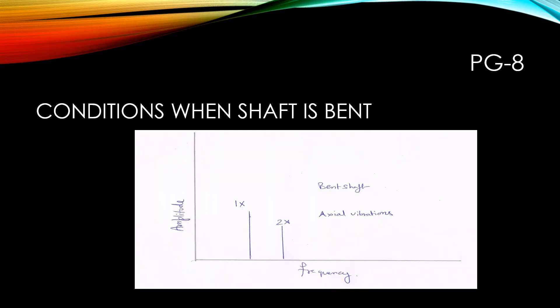Now the case where there is a bent in the shaft. When the shaft bent is encountered, the vibration in the radial as well as in the axial direction will be high. The axial vibration may be higher than the radial vibrations. The spectrum analysis will normally have 1x and 2x components. If the amplitude of 1x RPM is dominant, then the bent is near the shaft center.